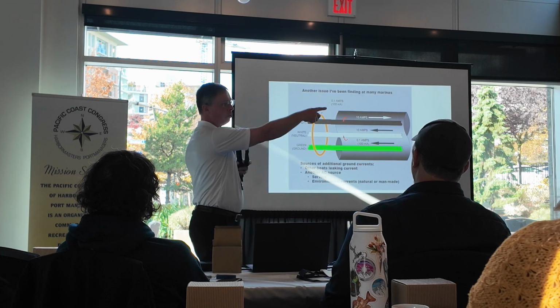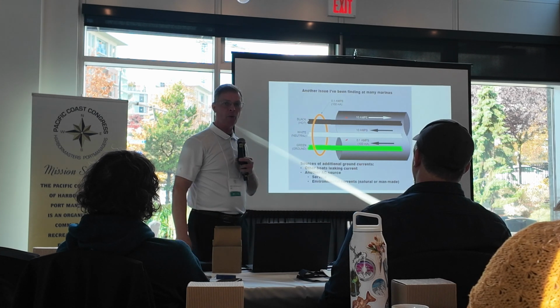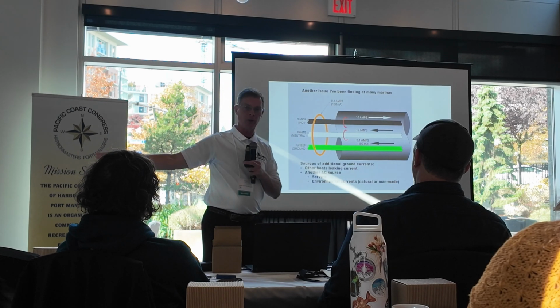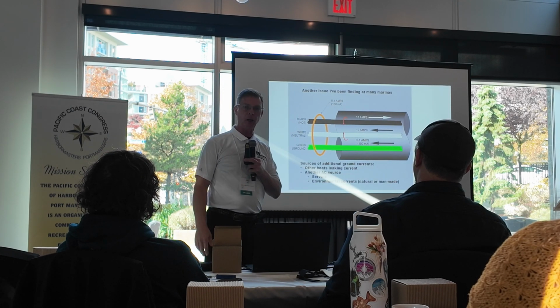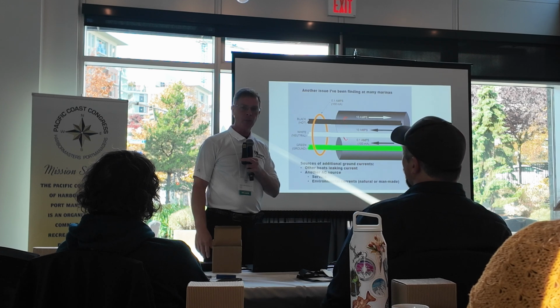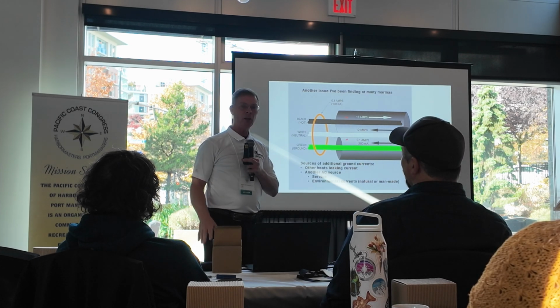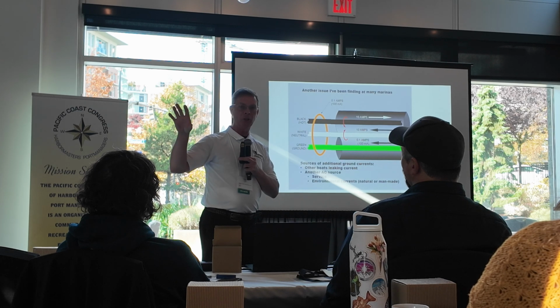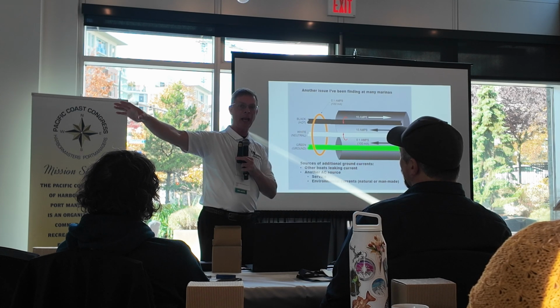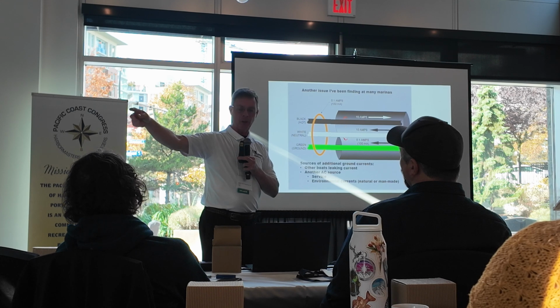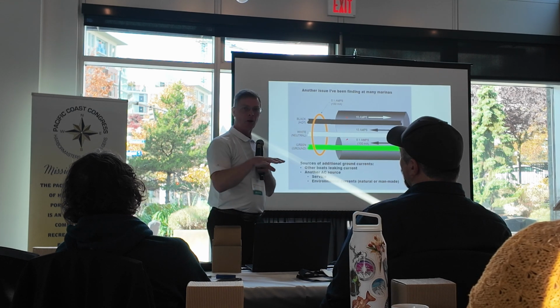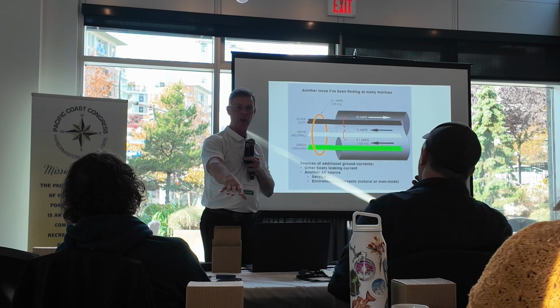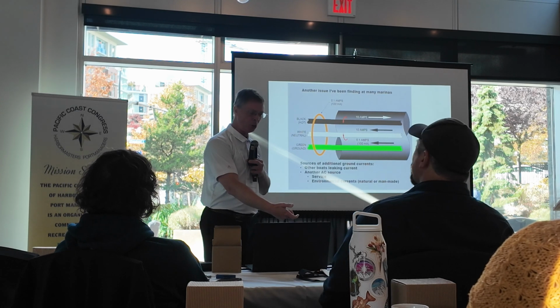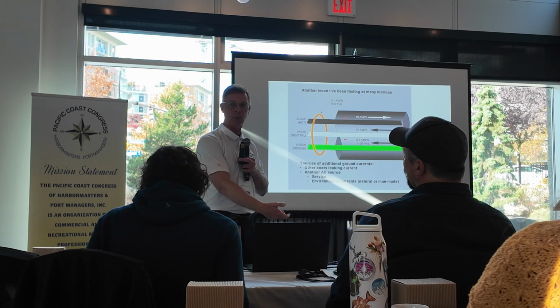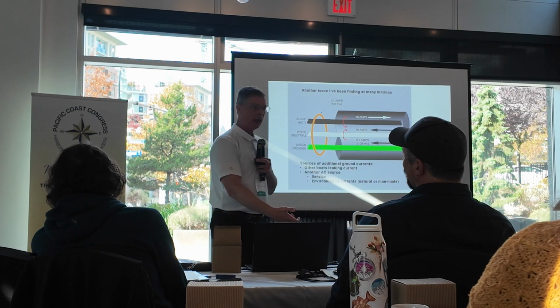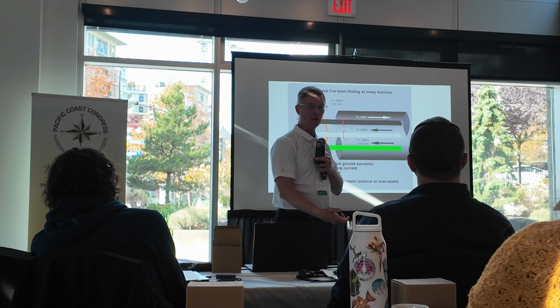He went back a mile down the road and pulled the jack out of the overhead service and killed the entire neighborhood a mile around us. Guess what I had on the ground wire? 2,000 milliamps of leakage current. We could not get rid of it, and wound up. It was actually in Tennessee. TVA had a generating dam, and it was coming through the utility, through the ground, back up. For the anchorage systems, they had dead men with stainless steel anchorage cables going out. And I was measuring 200 to 300 milliamps on the anchorage cables, coming from the bottom of the lake. And that is a man-made current in the lake.